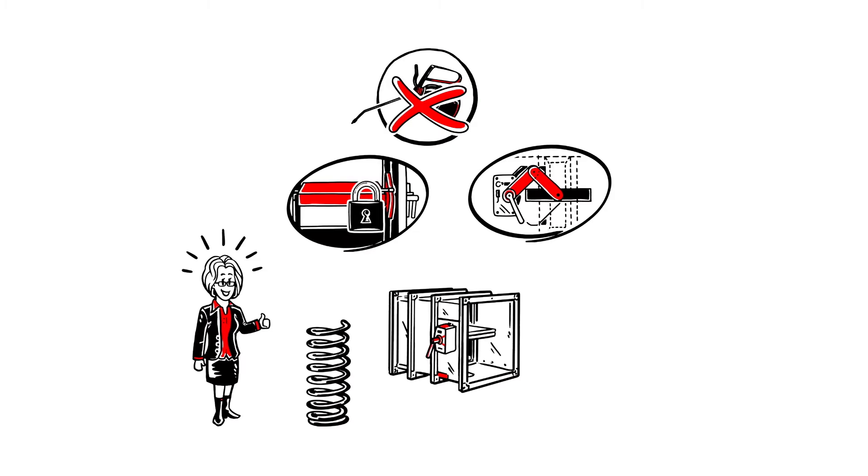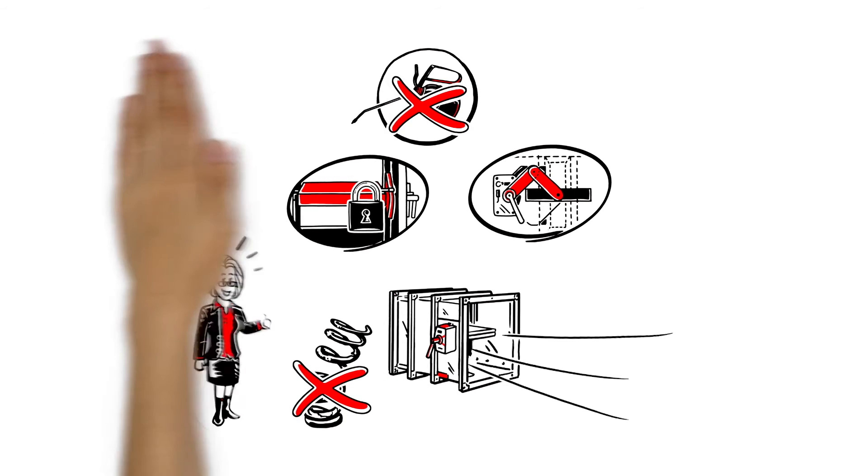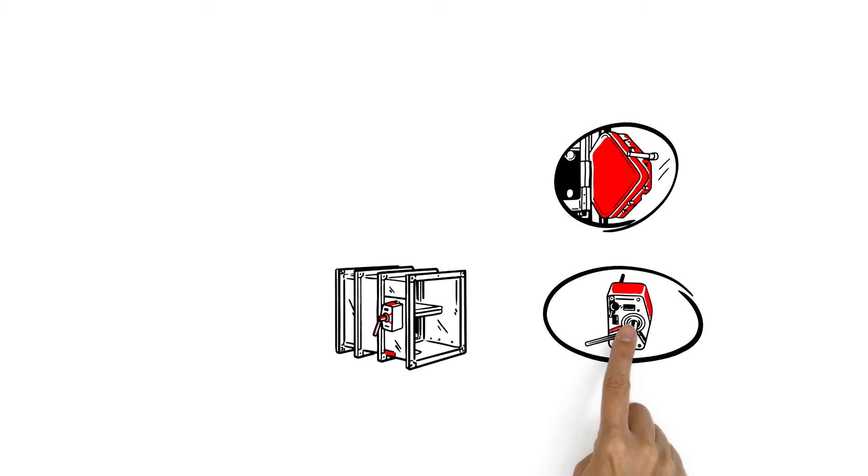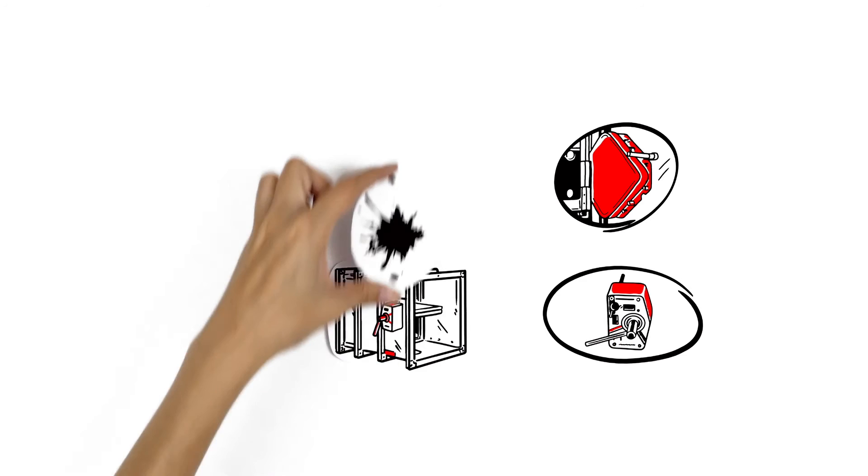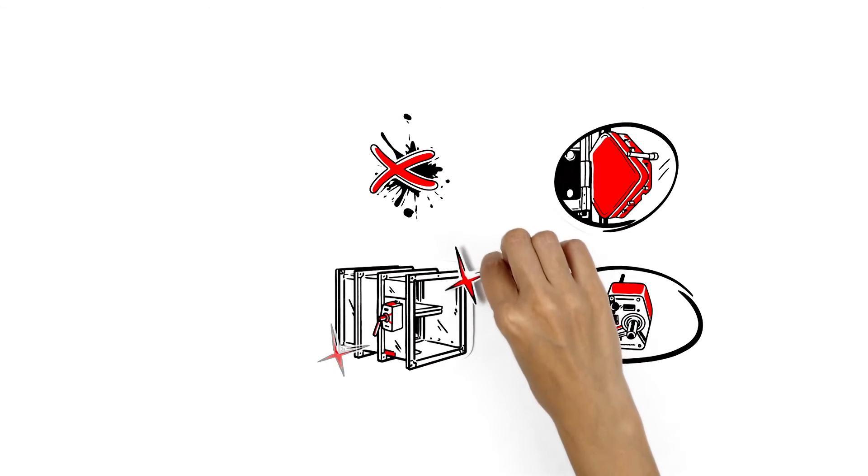Drive linkages that are exposed to the airflow and whose springs could lose tension are not used here. All the dampers mechanical components are fully enclosed. They are thus completely protected from dirt and impurities and permanently lubricated.